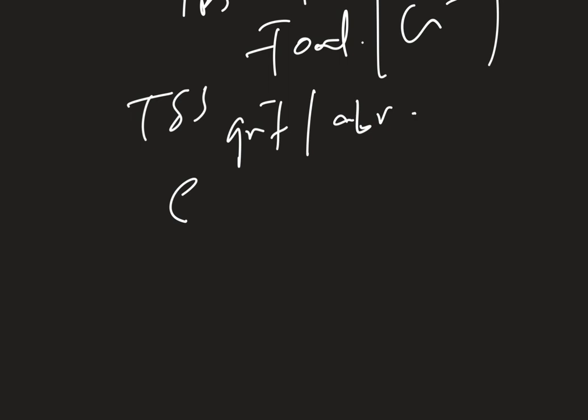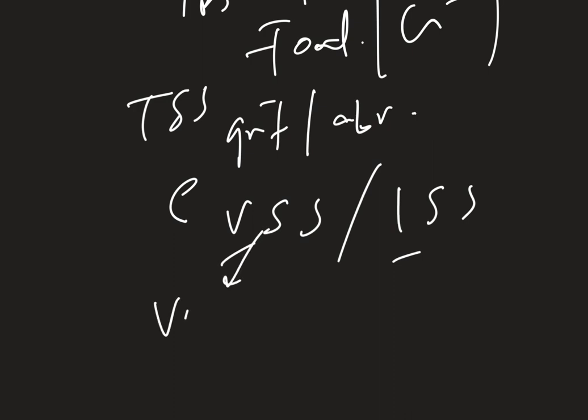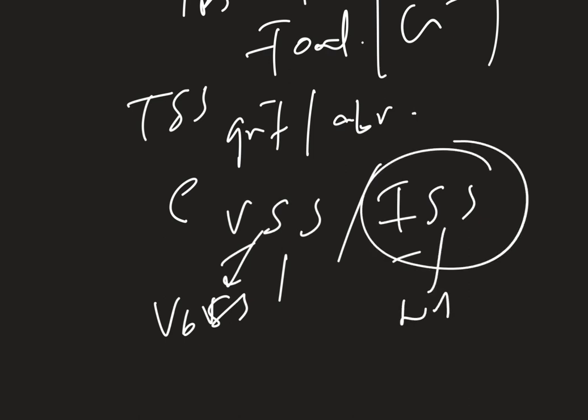So for total solids you can have VSS and ISS. ISS is inorganic, VSS is volatile. Volatile means organic, but volatile doesn't mean that it's biodegradable. Some are non-biodegradable. ISS definitely is not biodegradable, like bone and things like that. So these are the things that cannot be removed by biological process. This may or may not apply to the VSS. These are physical parameters that you need to take care of.